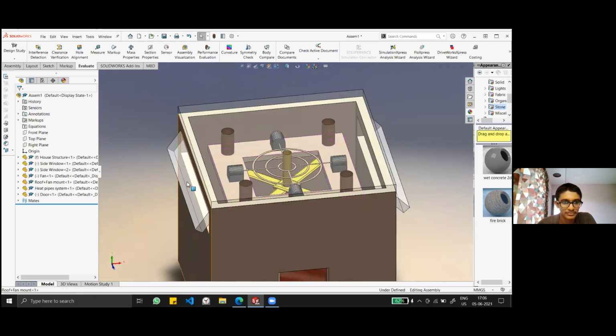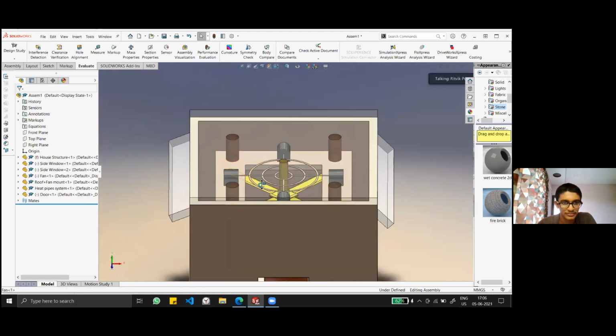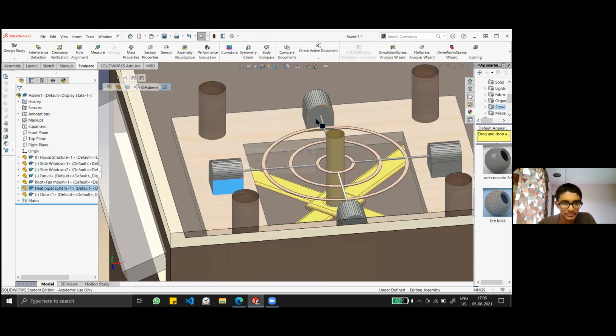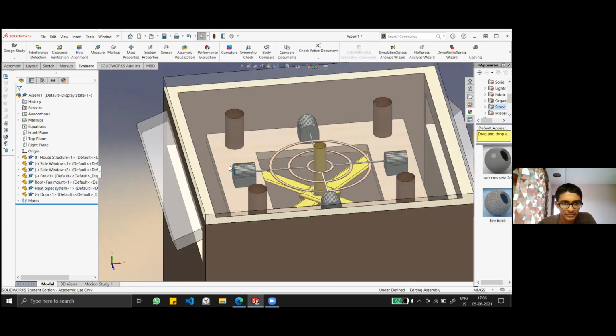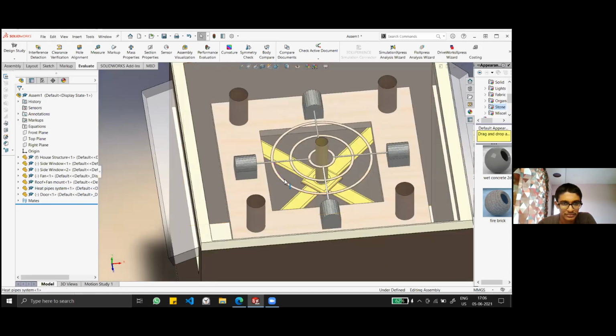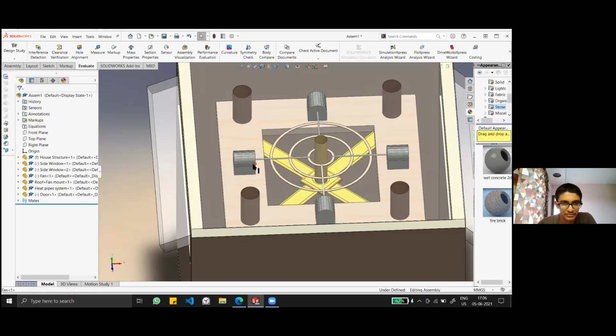So during the night, these vents, fenestrations, are opened to allow the cold night wind to enter the space. These containers, as you can see here, contain what is known as a phase change material. A phase change material has certain properties that we will be using. I'll get into those later. Once these phase change materials get hold of this night wind, they freeze. They freeze at night, and during the day, due to the warm temperature outside, they melt, and in the process, they absorb the heat from this inside room.